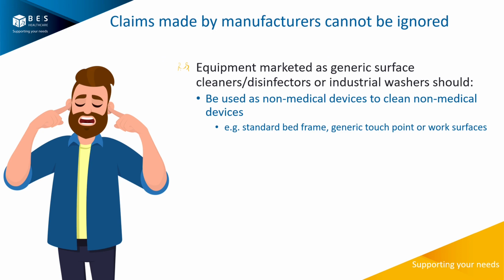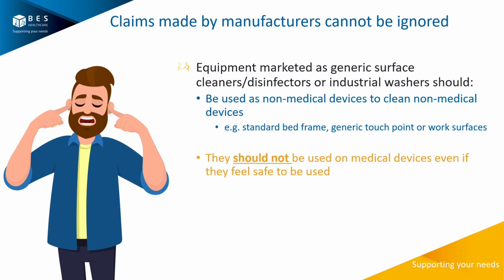It's also important to be careful about how and what manufacturers are claiming. Equipment that is marketed as generic surface cleaners, generic surface disinfectors or industrial washers can be used on non-medical devices. That's what they're intended for. So something like a generic bed frame is not a medical device, or touch points and work surfaces around a loan store, you can use such things, there's no problem with that. But these same devices, chemicals or machines should not be used on medical devices, even if you have done in the past or you feel that it is safe to do so.